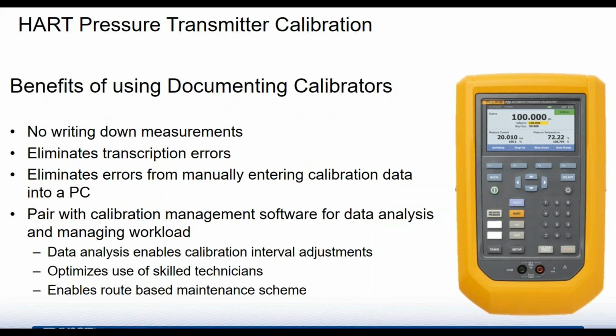So let's take a look at what we can accomplish using those documenting calibrators. For one, when you go out in the field and you've got a piece of paper and a pencil, you've got to write down all those measurements, all the results. You've got to figure out if it's in spec or not. You don't have to do that with a documenting calibrator. It electronically captures all that information and lets you know if it's in spec or not.